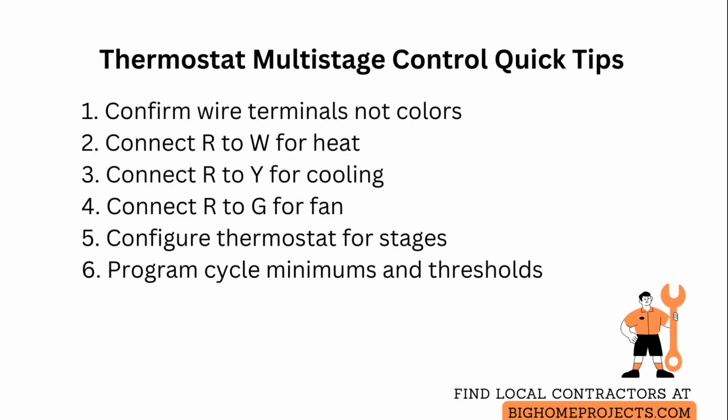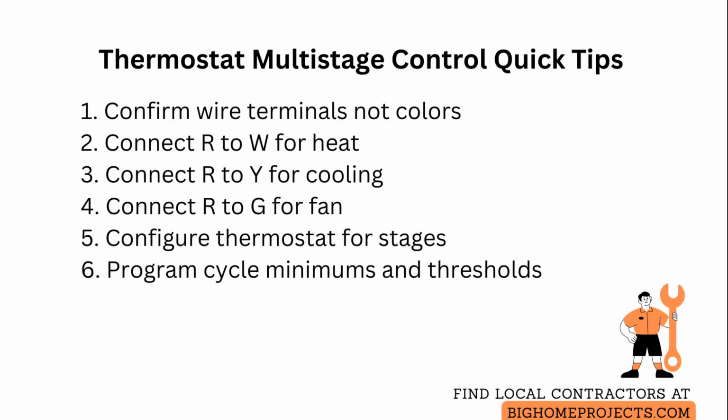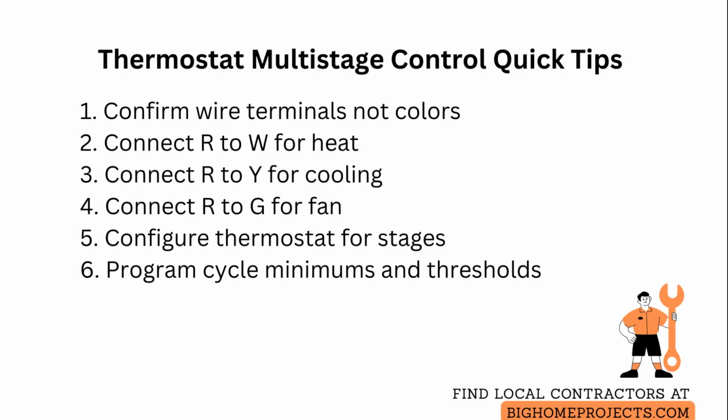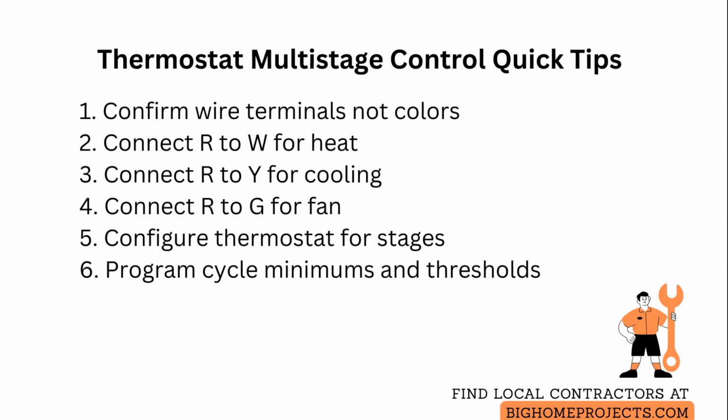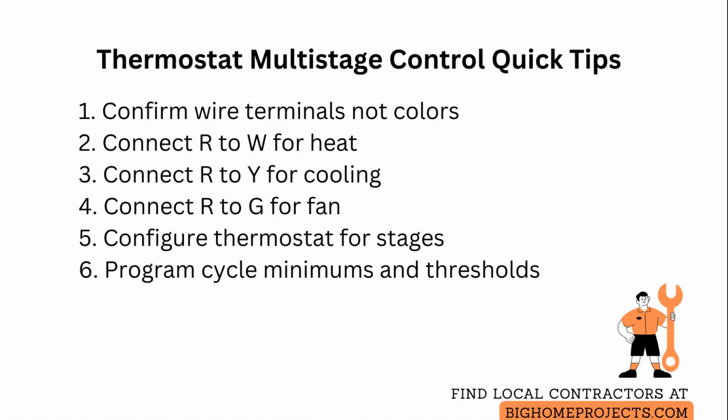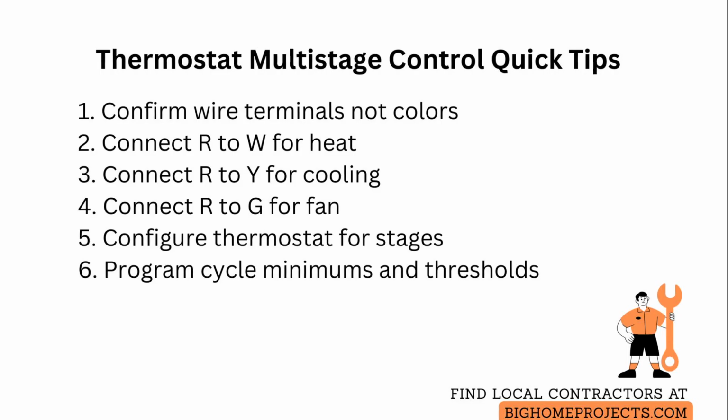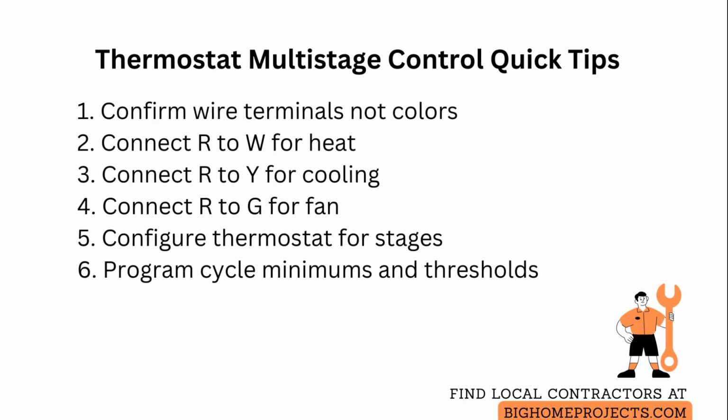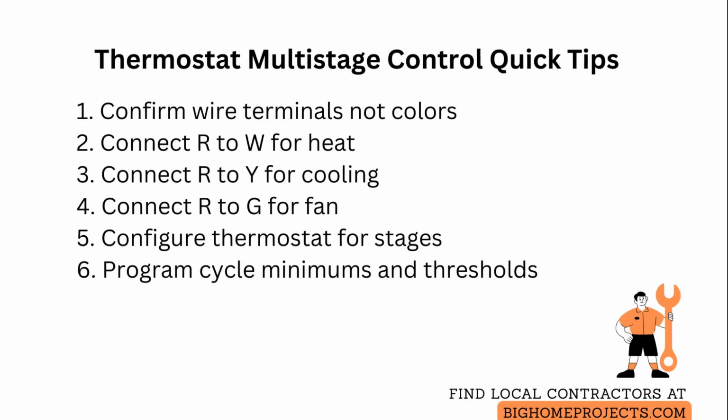During a heating call, confirm the heat source control receives the heat demand signal and any sequence delays are observed so the system does not short cycle. For multi-stage operation, allow the thermostat to use a stage lockout and a minimum runtime to prevent rapid toggling, and set temperature differentials, or staging thresholds, to match manufacturer guidance. So each stage runs long enough to affect room temperature.